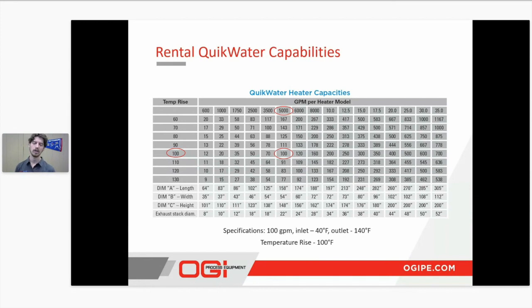As well, we can adjust that flow rate to whatever we need, as long as it fits on the pump curve of the transfer pump that we have specified within it. Always happy to put a globe valve on the discharge to essentially lessen that flow. It puts more back pressure on that pump. If you only need about 90 gallons per minute, you don't want to overflow something.